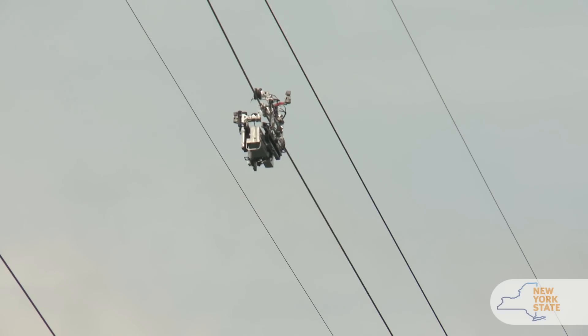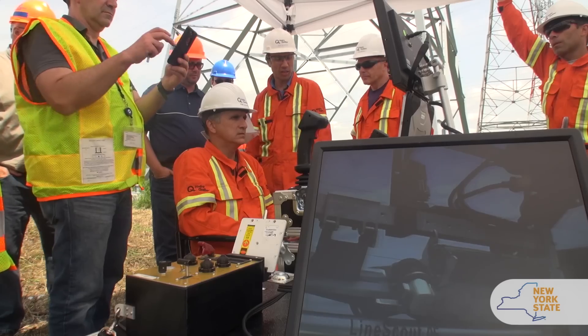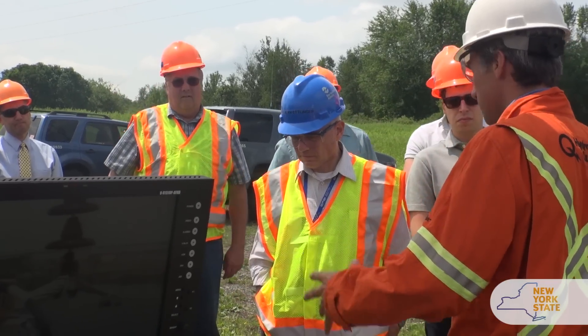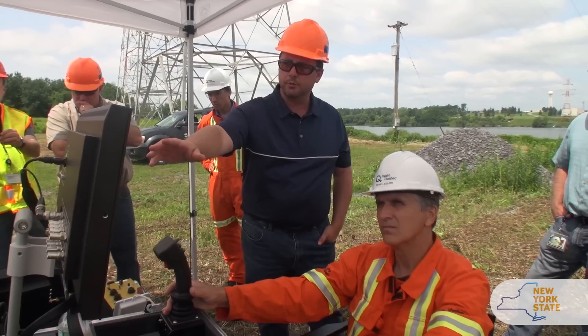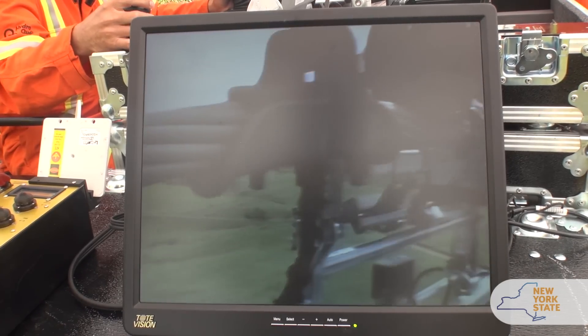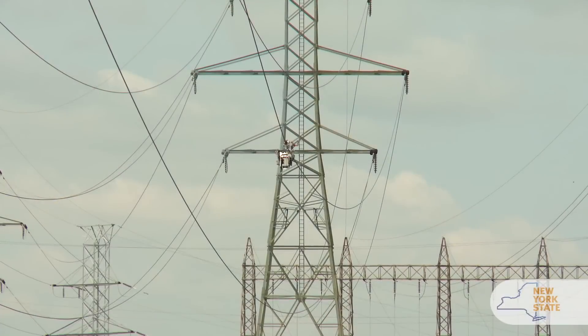The Line Scout is giving us really good quality pictures and the data we're looking at is really valuable. The results of today's inspection show that the lines are in very good shape. The quality of the pictures and how close we can get to the buckles, turnkeys, and bolts on the line is really good — detail we would not otherwise be able to obtain.